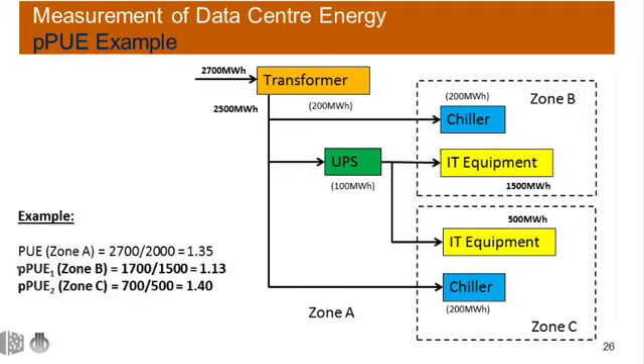Moving on to the next slide, this highlights how partial PUE differs from PUE. So if we take partial PUE1 or zone B as the first example, you can see we've got 1700 megawatt hours divided by 1500 megawatt hours. The 1700 comprises the IT load plus the absorbed power of the chiller, totaling 1700 megawatt hours. This equates to a partial PUE of 1.13.